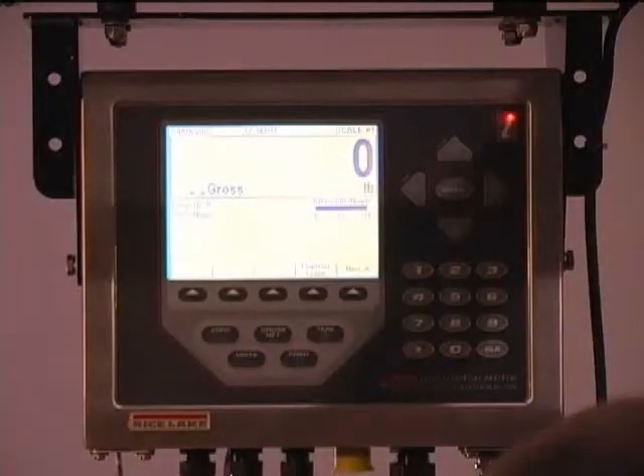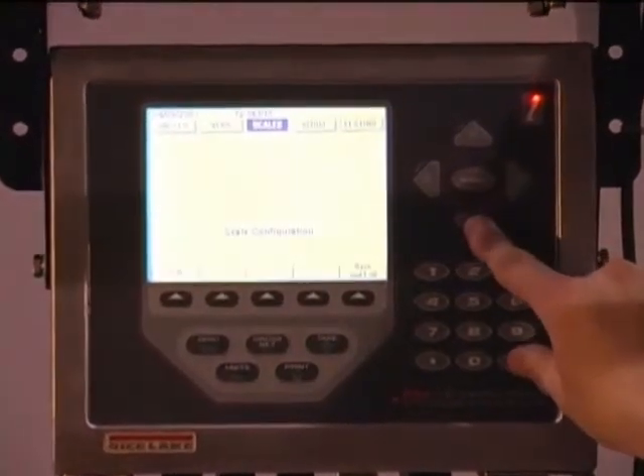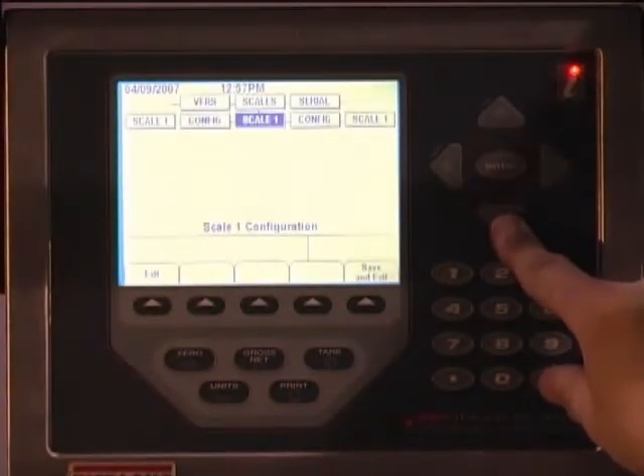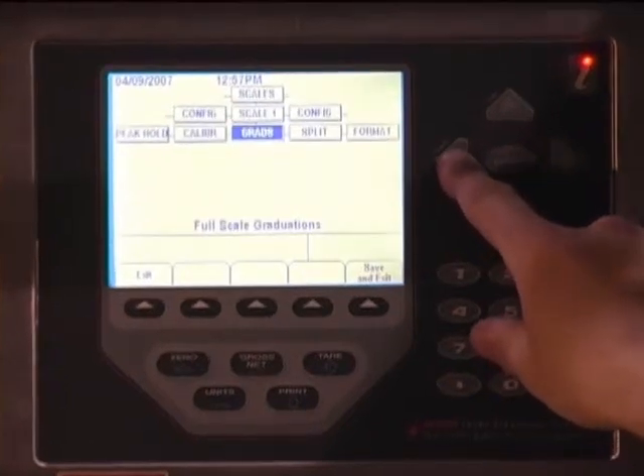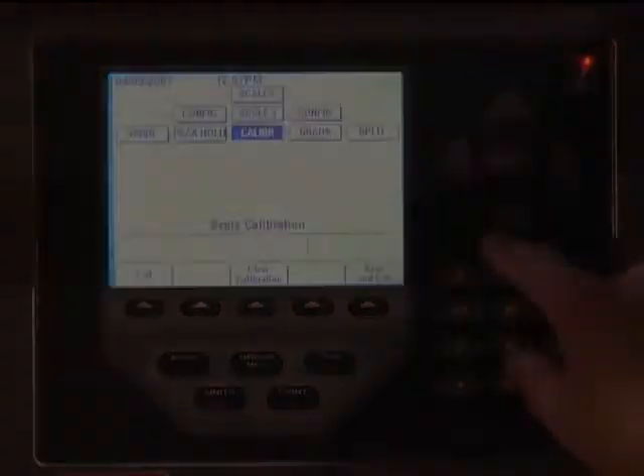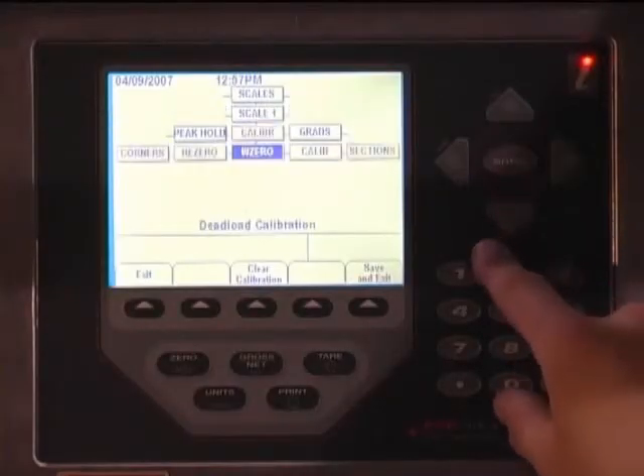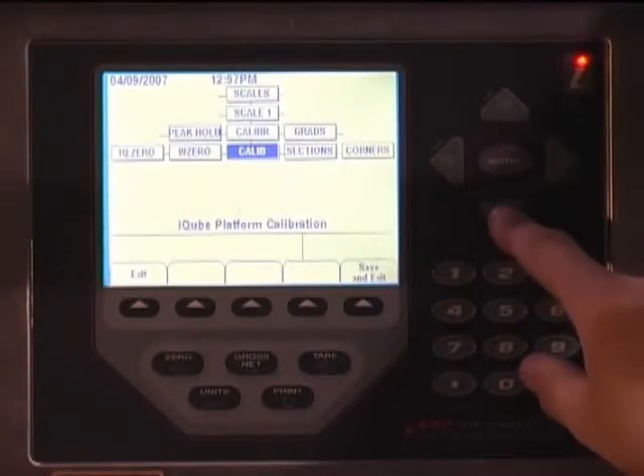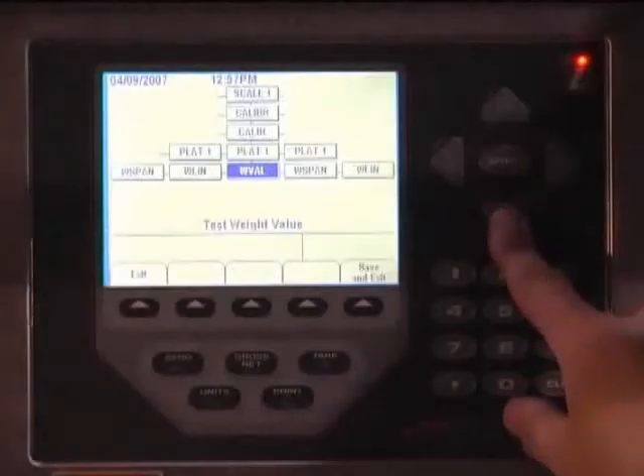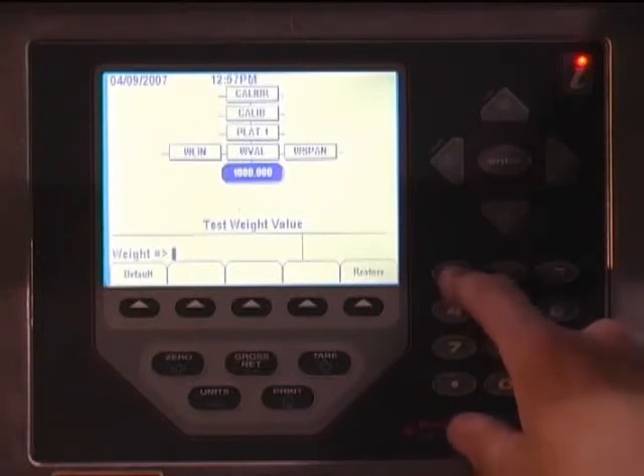Put the indicator into setup mode by pressing the indicator setup switch, which is located on the underside of the indicator. The indicator setup menu is displayed with Scales highlighted. Press the down key twice to highlight Grads, then press the left key once to calibrate. Press the down key once to WZERO, then the right key to calibrate. Press the down key three times to display the value of the test weight that will be used. Using the numeric keypad on the 920i, enter the value of the test weight and press the Enter key.